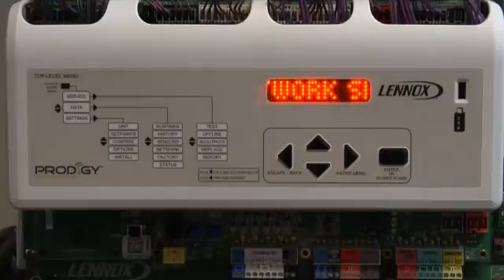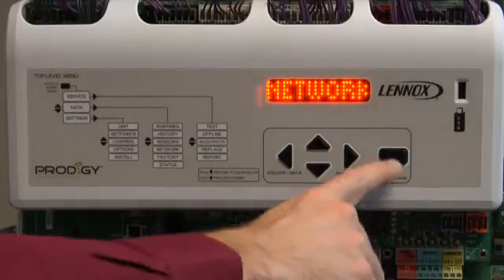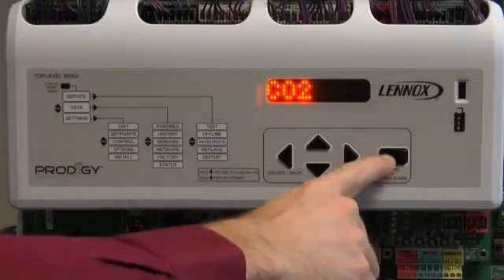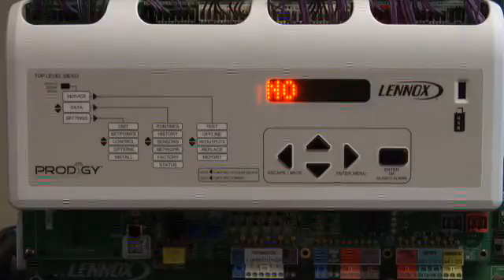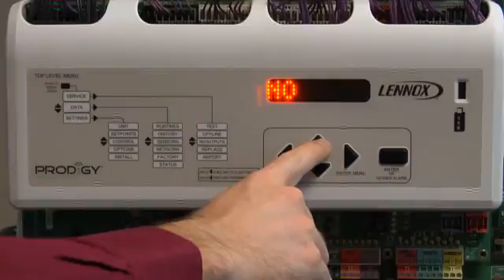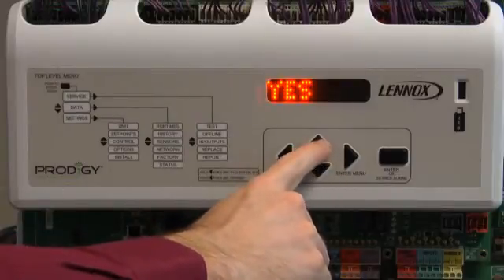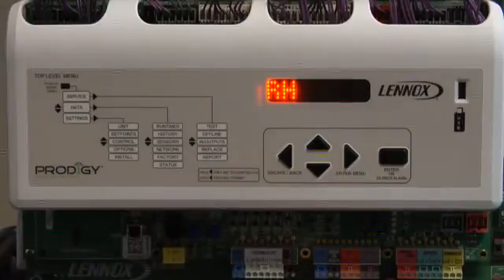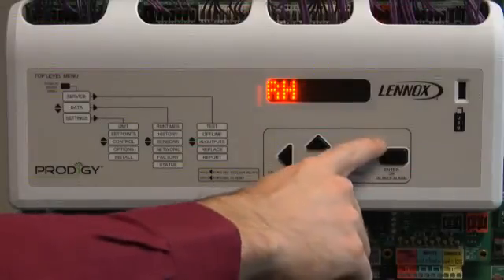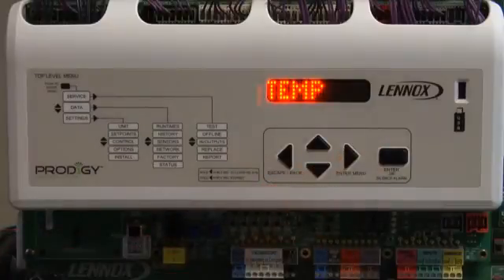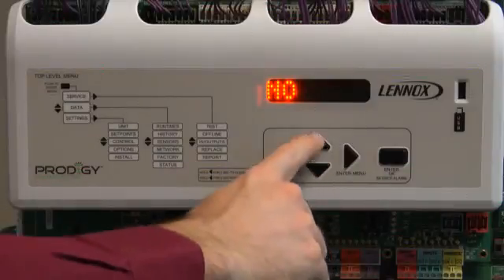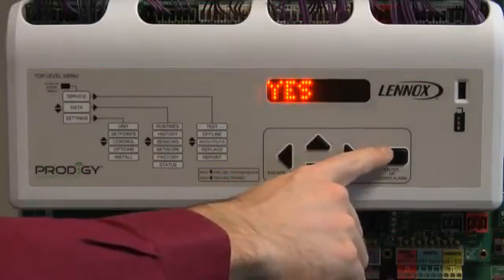Network sensor will be displayed. Press enter. CO2 will be displayed. Press enter. No will be displayed. Use the up or down arrow to change to Yes if you have a network CO2 sensor, then press enter. RH will be displayed. Press enter. Use the up or down arrow to change to Yes if you have a network temperature sensor, then press enter.